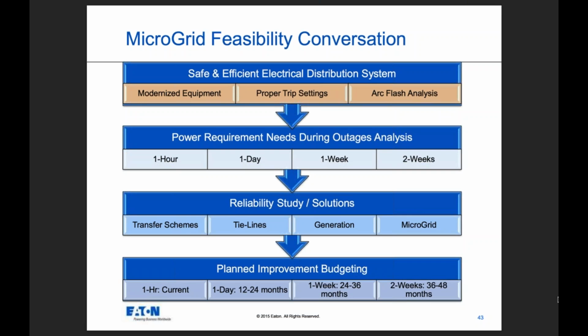By doing a study, by having someone step back and study your whole system, it identifies those kinds of things. It wasn't a difficult fix. They had to replace the transformer, which they did on an emergency basis, but we said you need to add its own circuit breaker there now, or fuse disconnect switch, so that if that transformer fails in the future, that device opens and you're not tripping the whole facility.